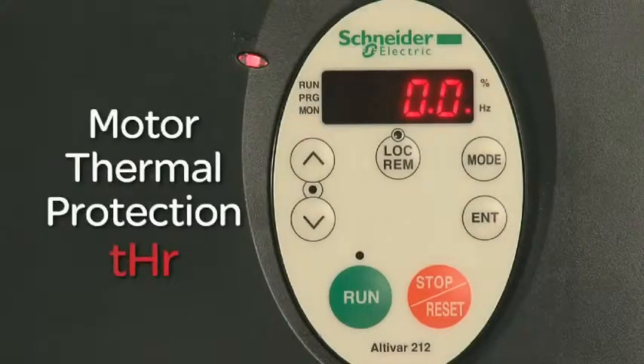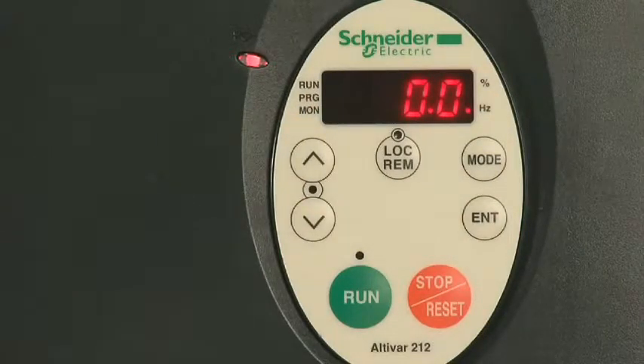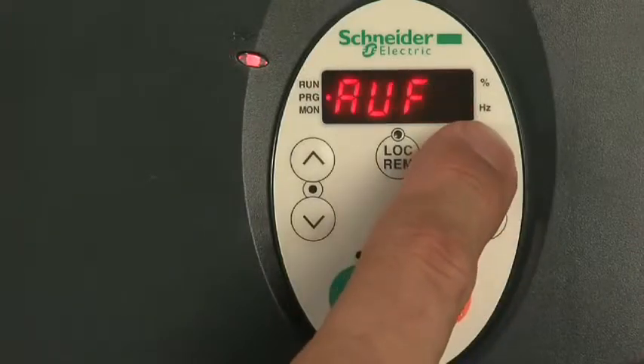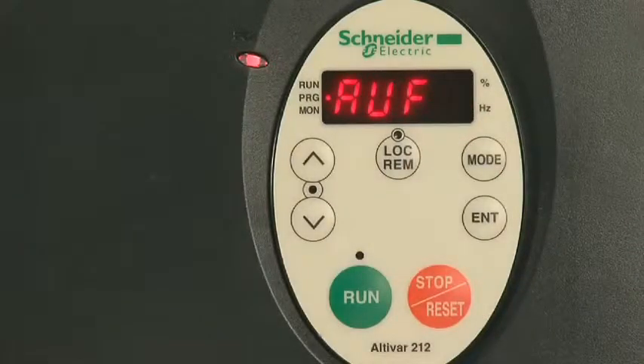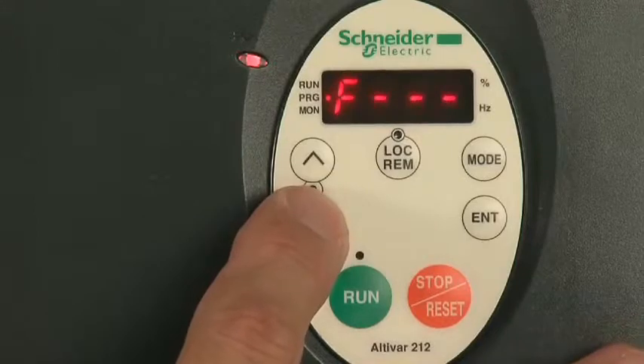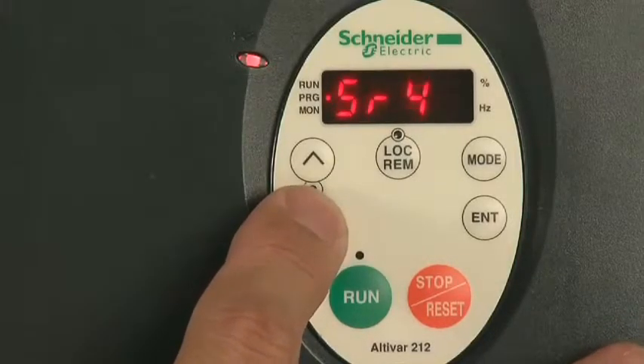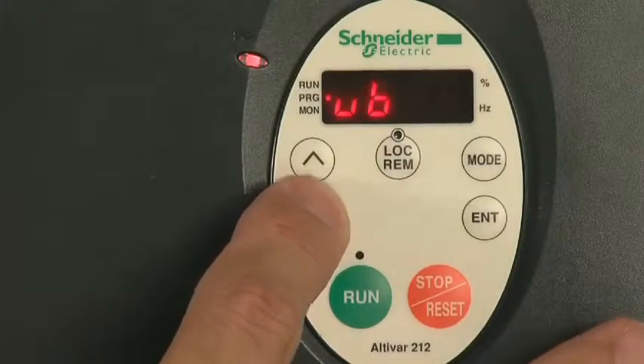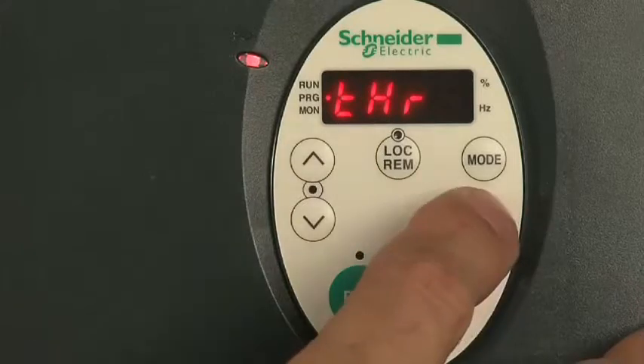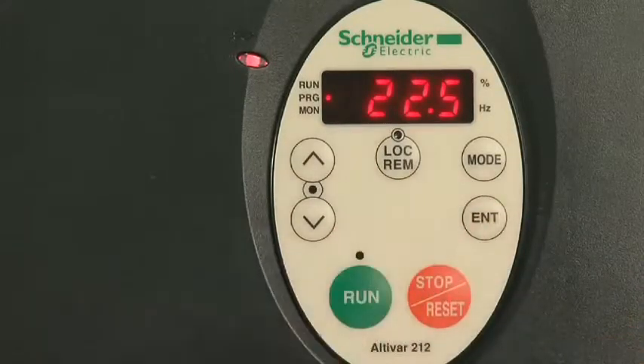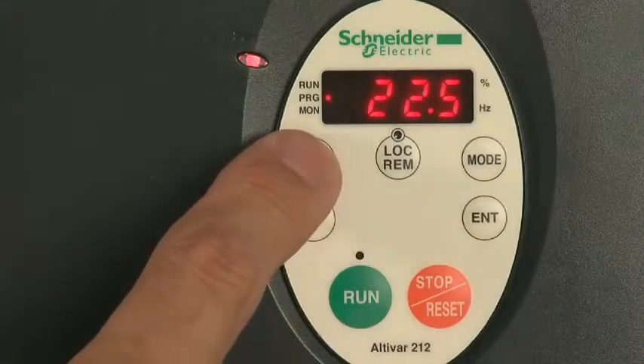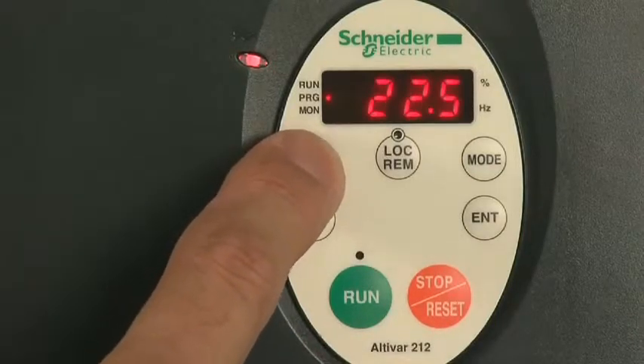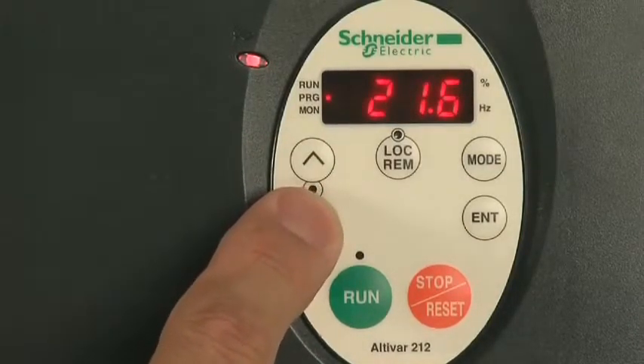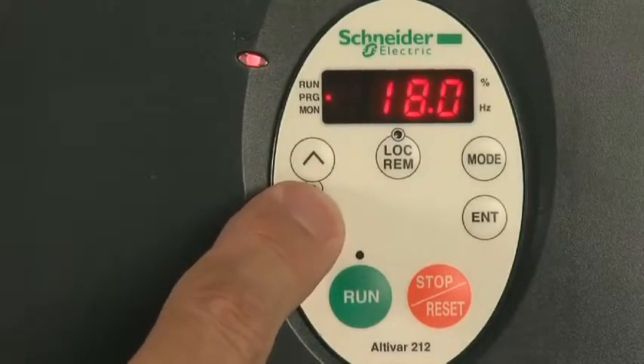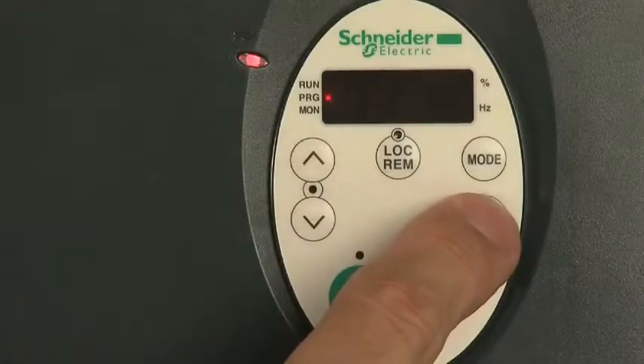Next, we will configure the motor thermal protection, labeled THR. Push the Mode button, which will bring you into the programming mode. With AUF displayed, navigate down 13 steps to THR. Press ENT. Use the arrow keys to navigate to the correct value equal to your motor thermal protection setting. Press ENT. This value will be set in amps.